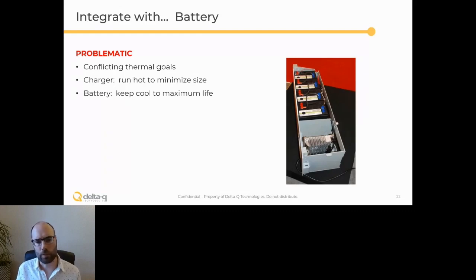The battery usually has the opposite goal — it's kept cool, around room temperature, to maximize life. A battery is an electrochemical device, so the rule of thumb is that for every 7 to 10 Celsius increase in battery temperature, you cut the calendar life in half. So you wouldn't want a 20 Celsius battery next to a 60 or 80 Celsius heatsink.